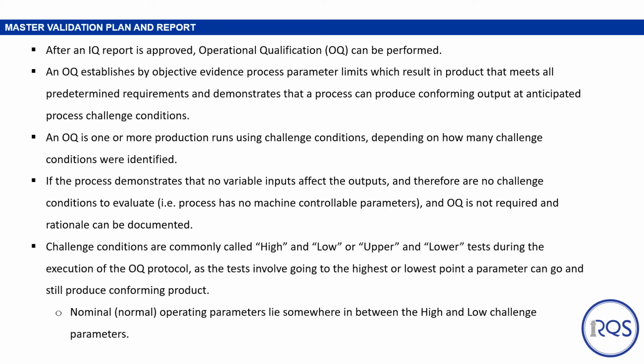After an IQ report is approved, operational qualification or OQ can be performed. An OQ establishes by objective evidence process parameter limits, which can result in product that meets all predetermined requirements, and demonstrates that a process can produce conforming product at anticipated process challenge conditions. And we established what challenge conditions were a little bit earlier. An OQ is one or more production runs using those challenge conditions, depending on how many challenge conditions were identified. So when you think of an OQ, think of pushing the limits of that equipment or process.